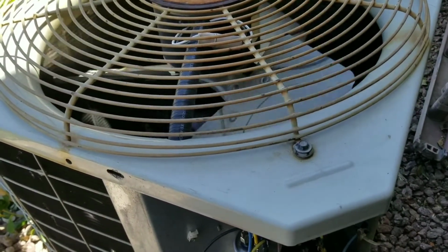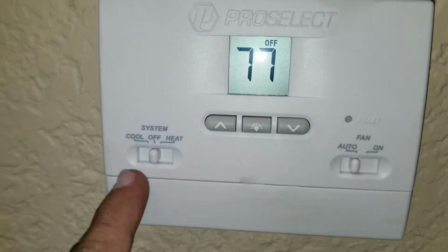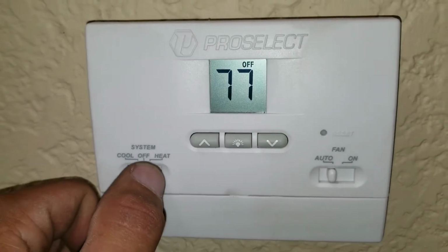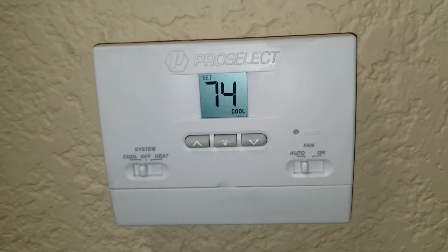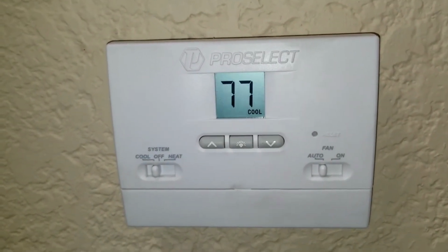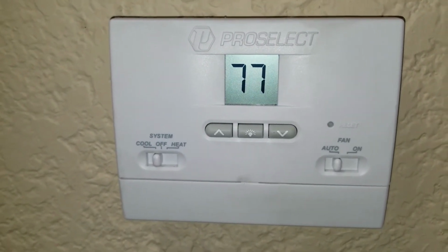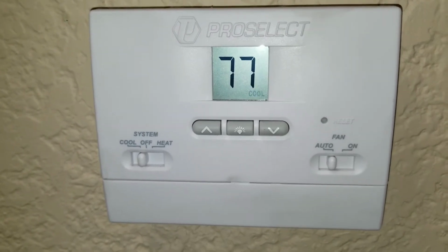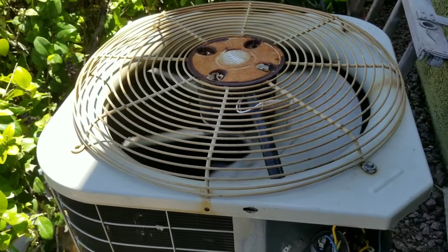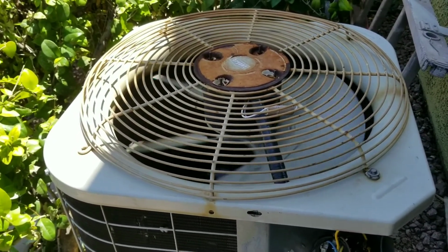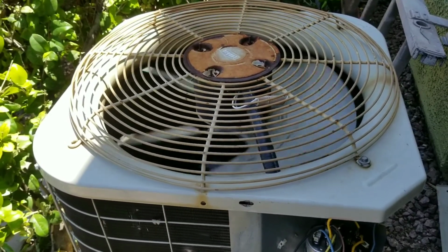So right now we're going to turn our thermostat on and see if our system functions properly. Here's our thermostat. It's in the off auto position. We're going to turn it to cool. Drop the temperature. We're at 74. The system should turn on. You heard it click. I hear my blower motor running upstairs. And now we're going to go outside and see if our condensing unit is running. You can see here my condensing unit is running. The fan motor is blowing. The condensing unit is operational. The compressor's on. So at this point, we know what the issue was: the contactor.